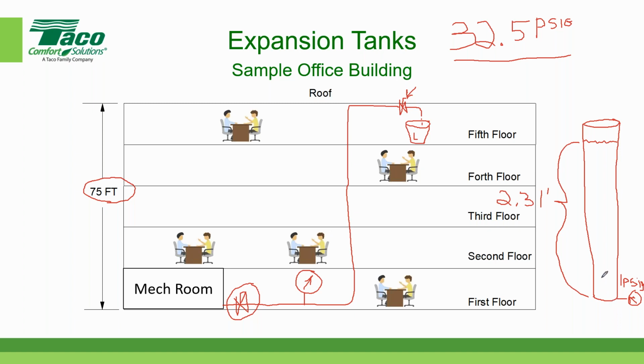So the relationship between the height of the fluid and the pressure is that every 2.31 feet gives you 1 PSIG. My building is 75 feet, and I simply took 75 divided by 2.31 and rounded it off to 32.5 PSIG. And someone typed that in, and they had the right answer.